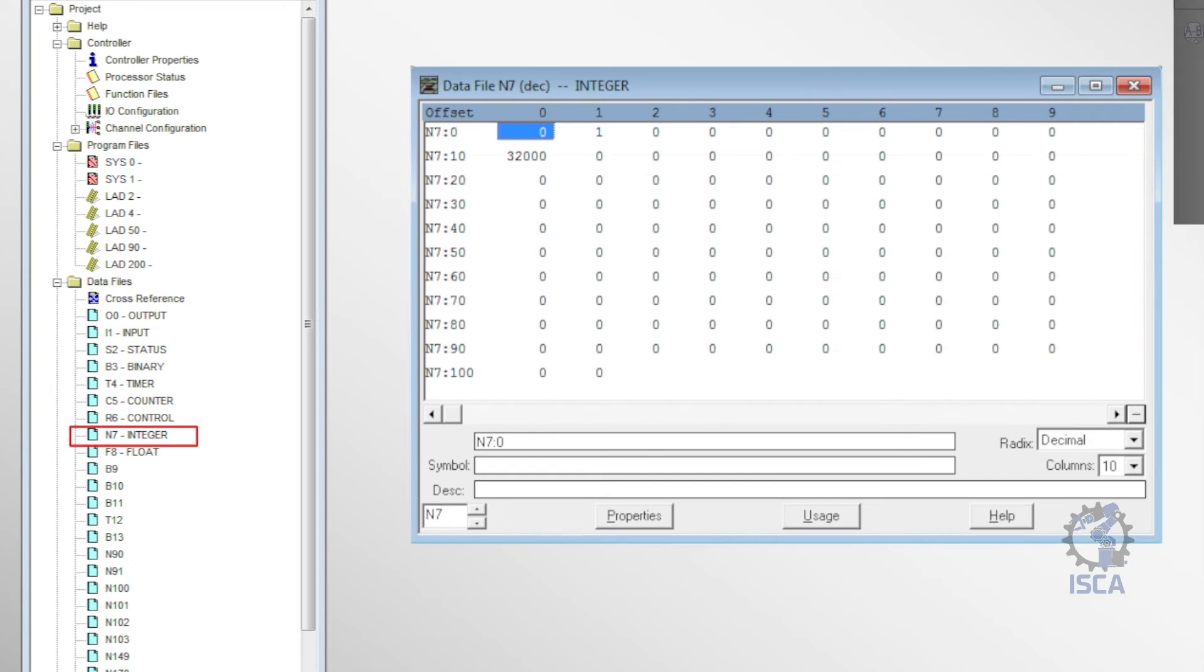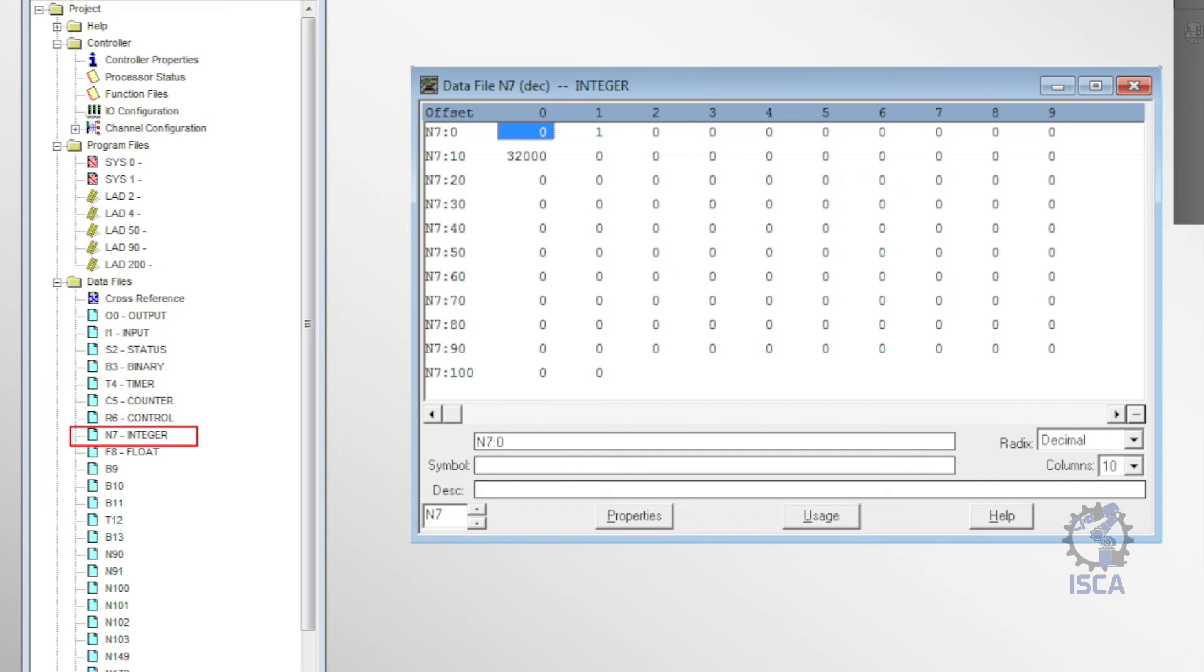N7 was the integer file, holding 16-bit integer values from negative 32,768 to 32,767 used in the PLC program.